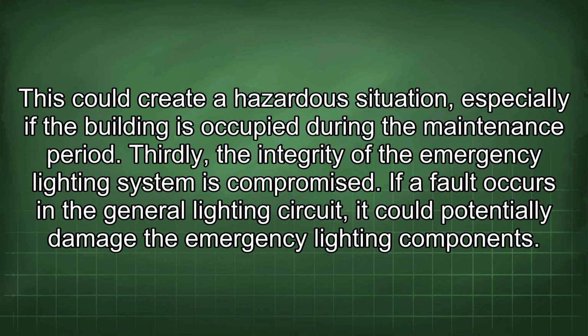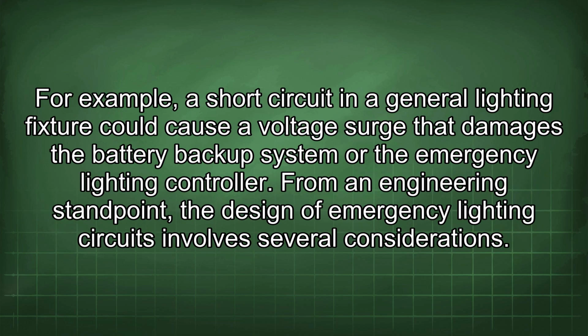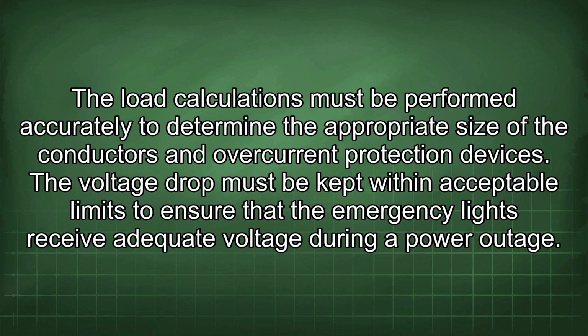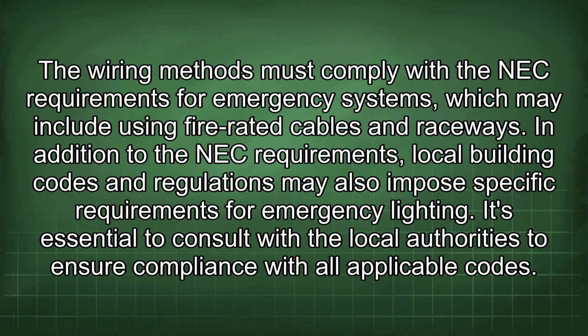Thirdly, the integrity of the emergency lighting system is compromised. If a fault occurs in the general lighting circuit, it could potentially damage the emergency lighting components. For example, a short circuit in a general lighting fixture could cause a voltage surge that damages the battery backup system or the emergency lighting controller. From an engineering standpoint, the design of emergency lighting circuits involves several considerations. The load calculations must be performed accurately to determine the appropriate size of the conductors and overcurrent protection devices. The voltage drop must be kept within acceptable limits to ensure that the emergency lights receive adequate voltage during a power outage.